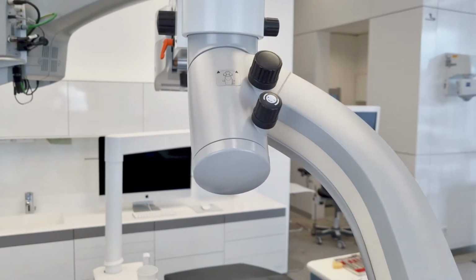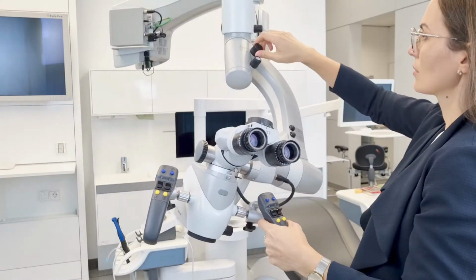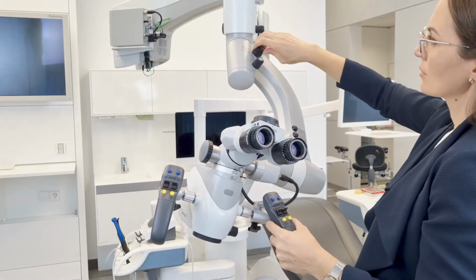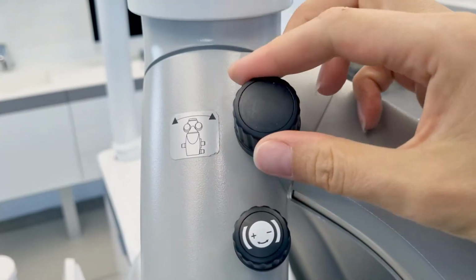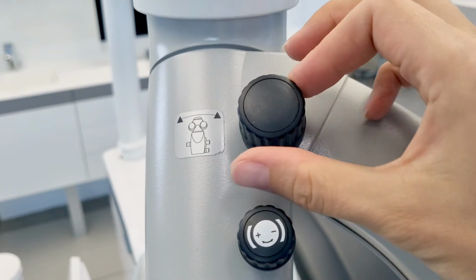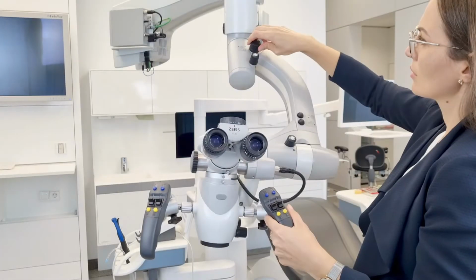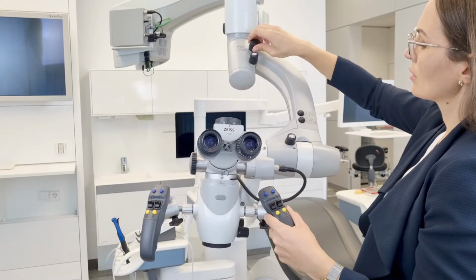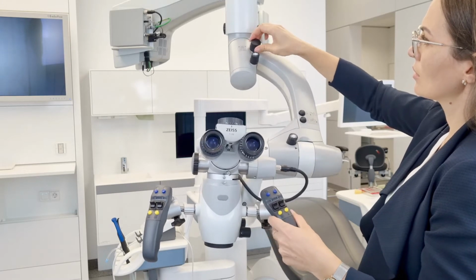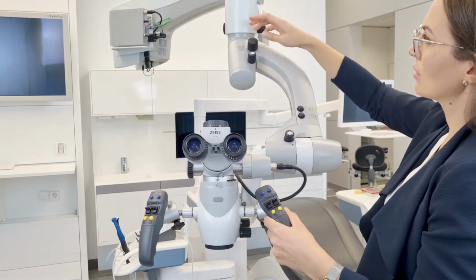Open the friction on the yoke. Turn the balancing knob on the yoke of the OPMI head. The OPMI should stay centered and not fall to the left or right side. Turn right if the OPMI head falls to the left side. Turn left if the OPMI head falls to the right side.